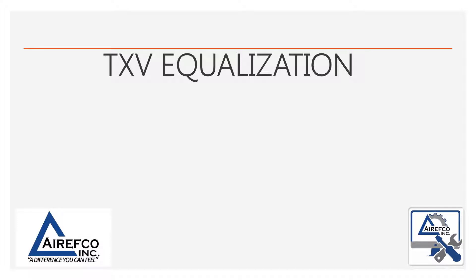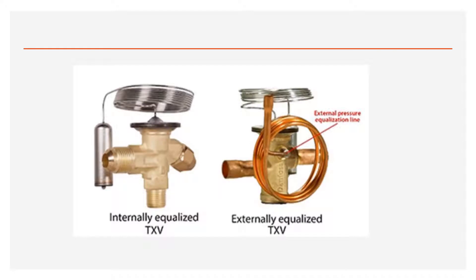TXV equalization, internal or external. It's fairly easy to distinguish an internally equalized TXV from an externally equalized TXV. The externally equalized TXV has a wrap of copper tubing, which is the equalization tube that needs to be routed on the other side or the outlet of the evaporator coil.